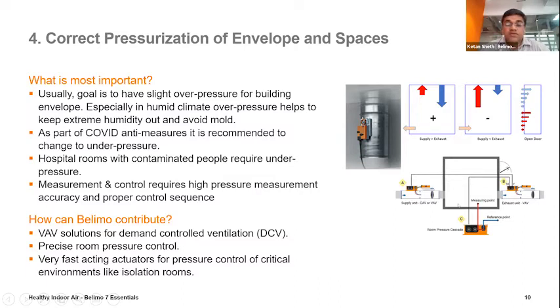Measurement and control requires a high pressure measurement and a quick control on that, because as soon as there is a pressure drop, there is a high chance of spread. So the pressure control in both the areas is very important. So again here the solution is the VAV solution for the demand control ventilation with a cascade control. You can see for the supply and exhaust, on the right hand side, with very good highly accurate sensors which help in achieving the precise room pressure control.